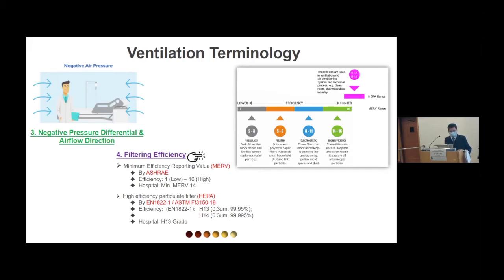The MERV rating is the American standard designed by the American Society of Heating, Refrigeration, and Air Conditioning Engineers, or in short, ASHRAE. Its value ranges from 1 to 16, with a higher value meaning higher filter efficiency. In Hong Kong, we usually use the HEPA rating, which is a European standard. And for hospital applications, filters with HEPA grade 13 or even 14 are generally used. For ventilation using filters, designers must be aware that the fan should be compatible for use with a MERV or HEPA filter, since the fan must be capable of generating sufficient power to move air through the filter. This also means higher energy cost to operate such fans.